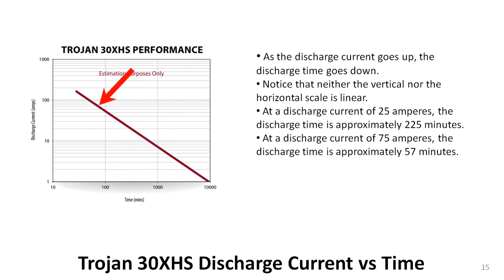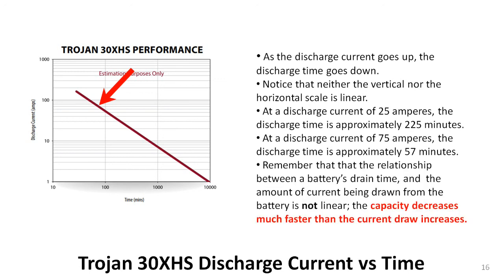If we move the red arrow to point to where the diagonal maroon line crosses the 75-amp horizontal line, it points to the 57-minute vertical line. That means that if the battery is discharged at a rate of 75 amperes, it will be completely discharged in only 57 minutes. Any other place along the diagonal maroon line will provide the discharge time at varying discharge rates. It's a graphical way of showing the relationship between discharge rates that we have already seen in the electrical characteristics table. This example also demonstrates again that the relationship between current drawn and discharge time is not linear. The capacity goes down much faster than the current goes up.